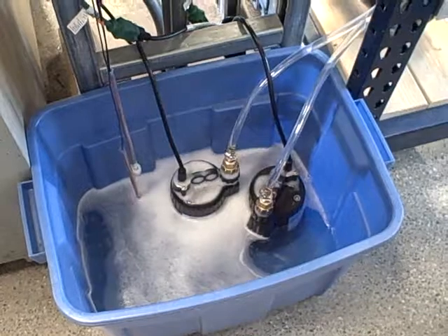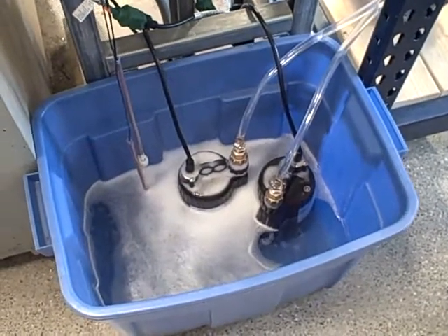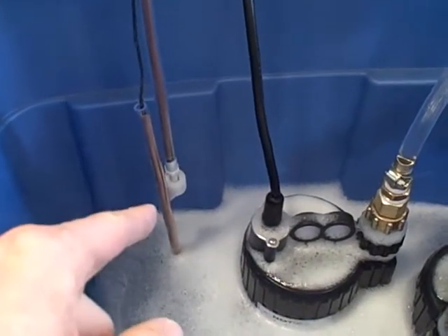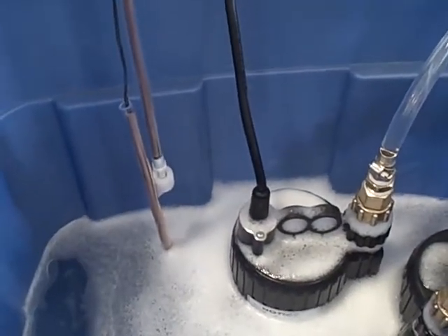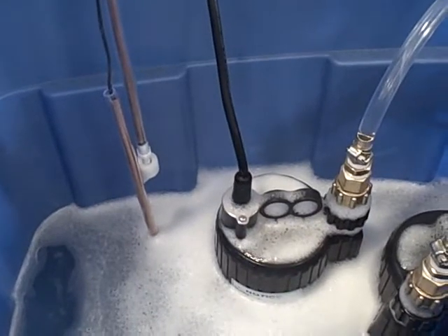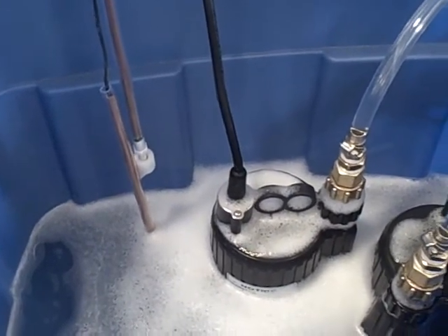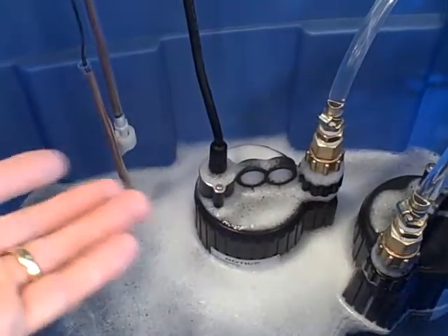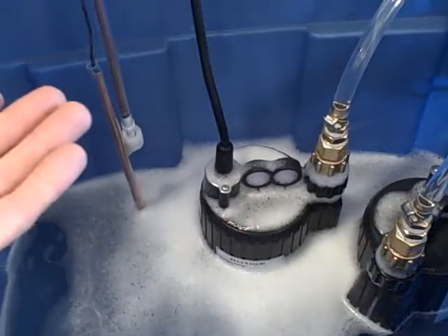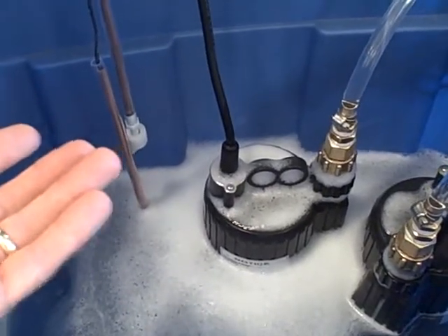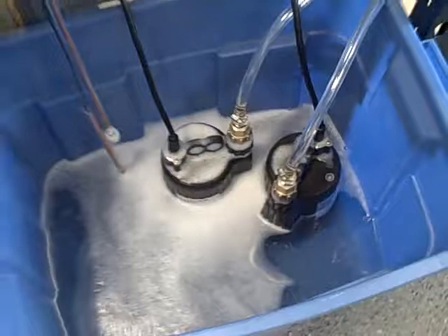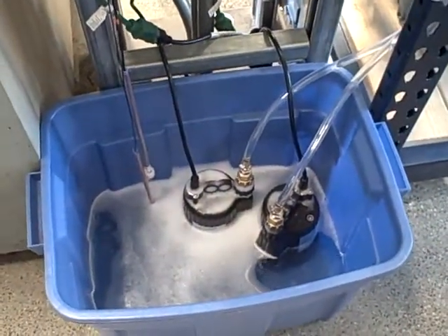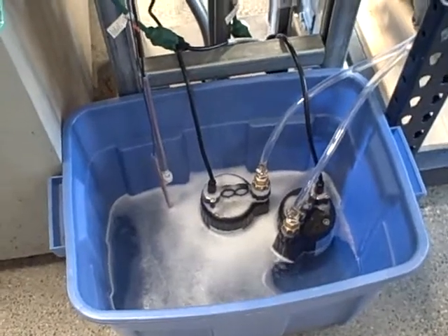Now, if for some reason the pump that turns on is not being very effective, and we retain a high level condition for a significant period of time, in this case a program time of 15 seconds, the PLC decides to turn both pumps on simultaneously, which is a feature that would come in handy, let's say, if one of the pumps were to fail. High level switch triggers, the pump doesn't come on because it's failed, and the high level condition persists. Then after 15 seconds it turns on the other pump. It thinks it's turning on both, but it turns on the other one. At least you have one pump running. At that point, we can also have the PLC flag an alarm and alert the operators as to the nature of the problem.